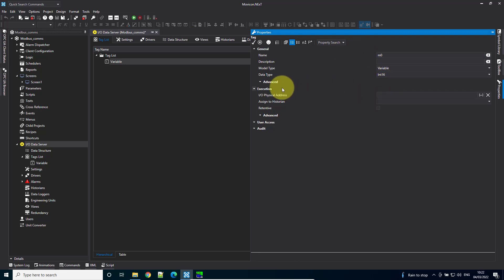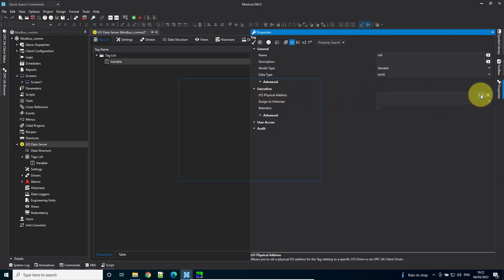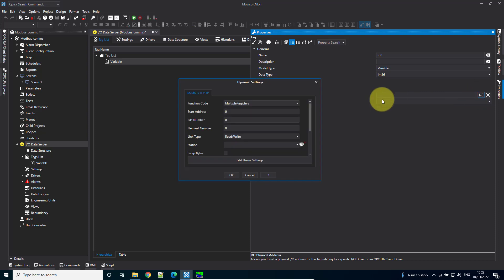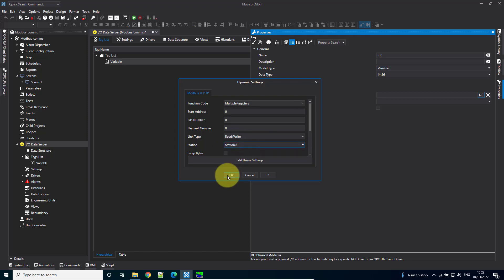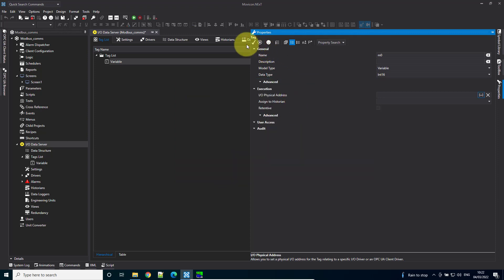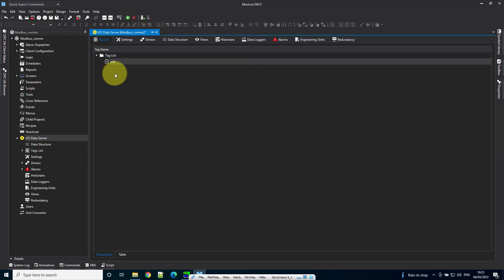To address it, come down to execution and IO physical address. Hit the three dots. We're looking at multiple registers, also called holding registers. Set the start address to 0 and the station to station 0. Hit OK and confirm.